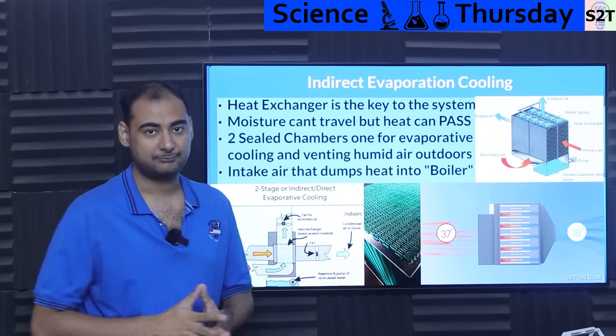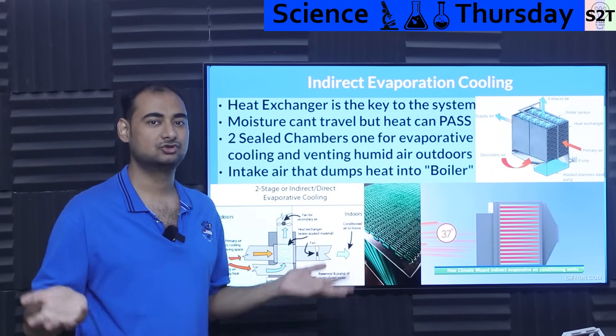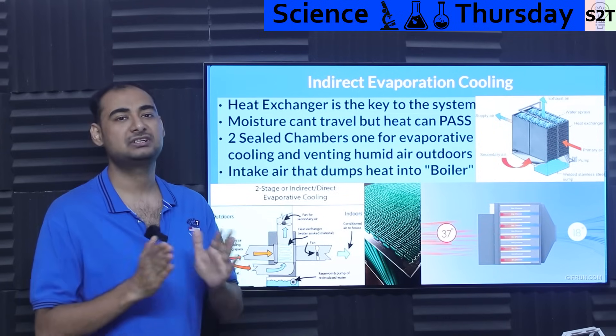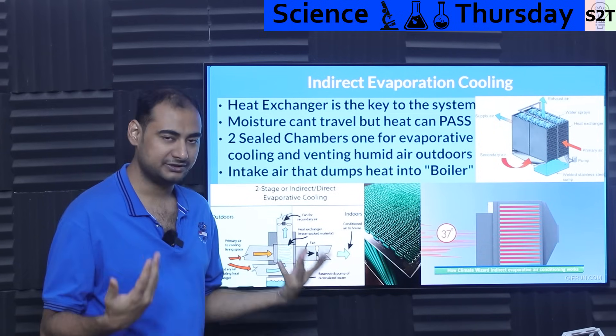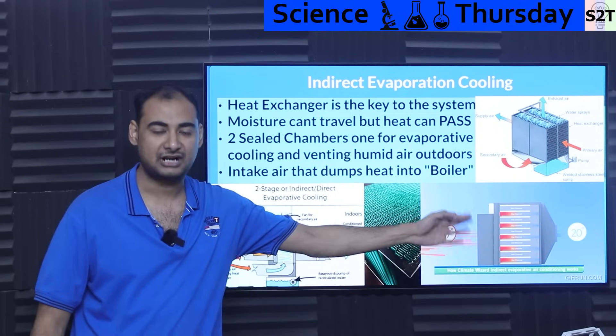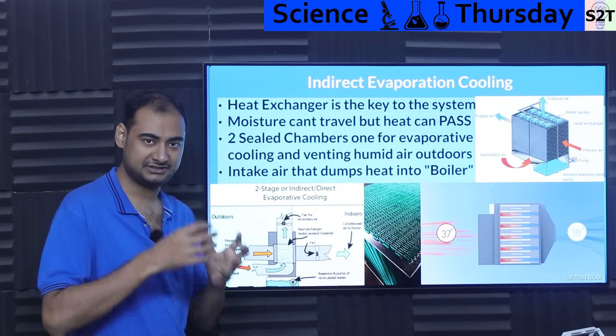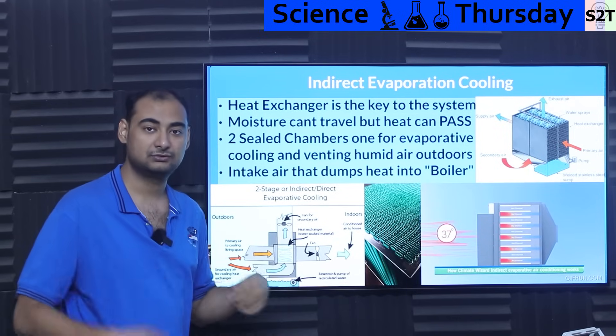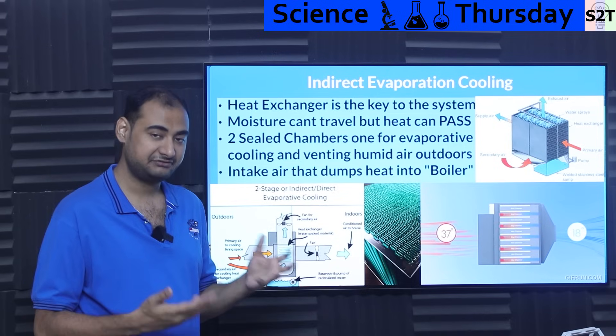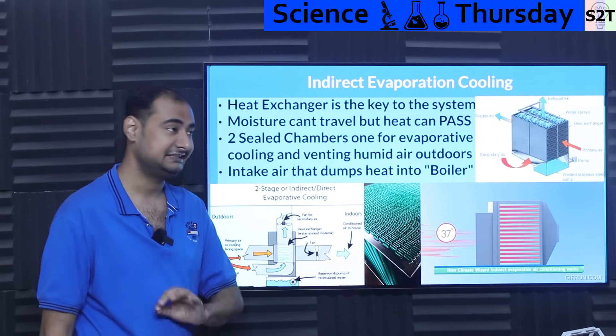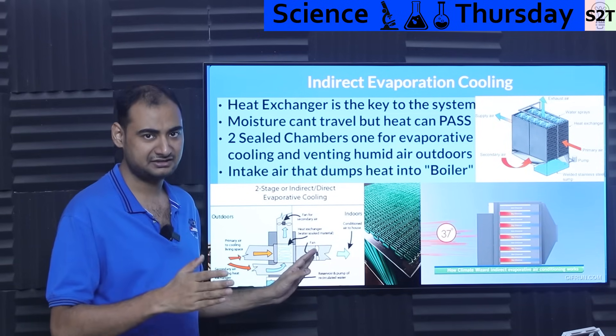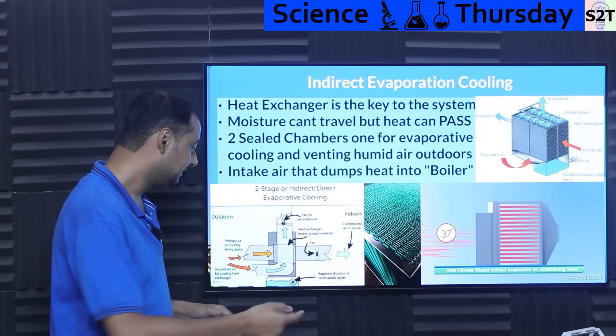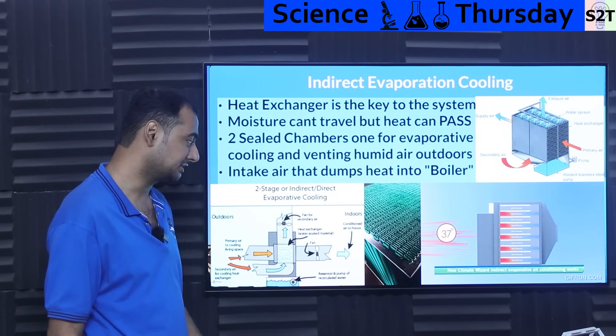So we come to indirect evaporative cooling. The idea is: what if we disassociate the two parts by putting a heat exchanger in the system? The key point of a heat exchanger is that moisture cannot pass from one side to the other, but heat can. You have dry channels and wet channels — air comes through, goes through the heat exchanger, cools down, and goes into your indoor space without adding any humidity.